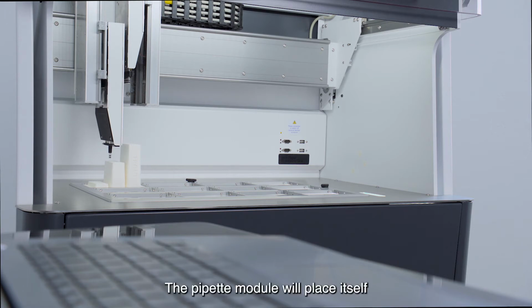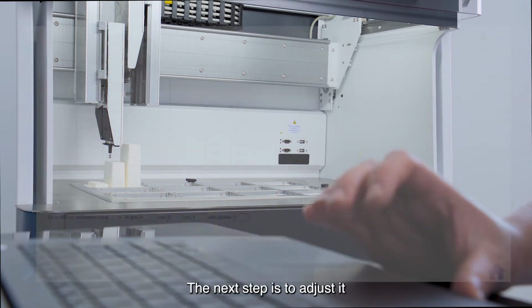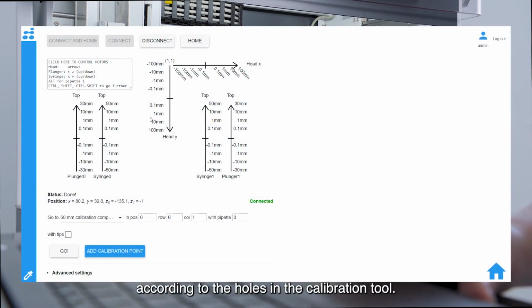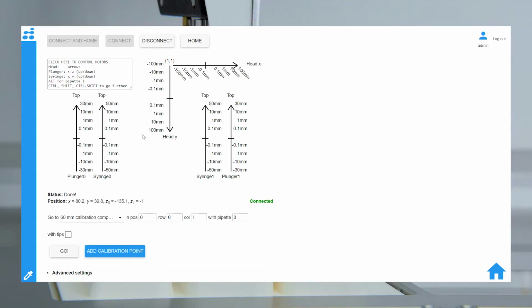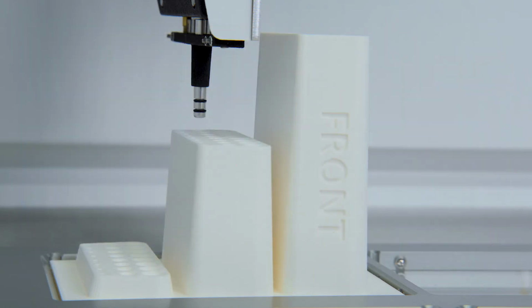The pipette module will place itself approximately 5 millimeters above the component. The next step here is to adjust it accordingly to the holes in the calibration tool. You can use the navigation controls to position the tip cone on the target position. You can adjust the syringe down 1 millimeter at a time until it is aligned with the surface of the target. So just at the same level, not into the well. You can use a piece of paper to adjust this.